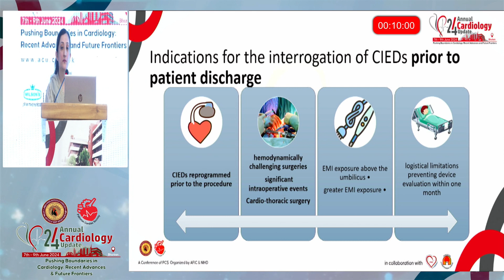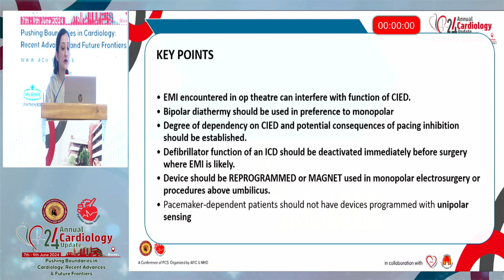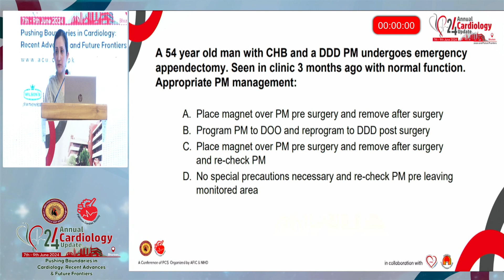The key points are that EMI encountered in the operation theater can interfere with device function. Bipolar diathermy should be used in preference to monopolar electrodiathermy. Degree of dependency on the device should be ascertained before the procedure. The defibrillator function of the ICD should be deactivated, and the device should be reprogrammed or a magnet should be applied in case of monopolar electrosurgery above the umbilicus. Pacemaker-dependent patients should not be programmed in unipolar sensing modes. So I will be closing this discussion.